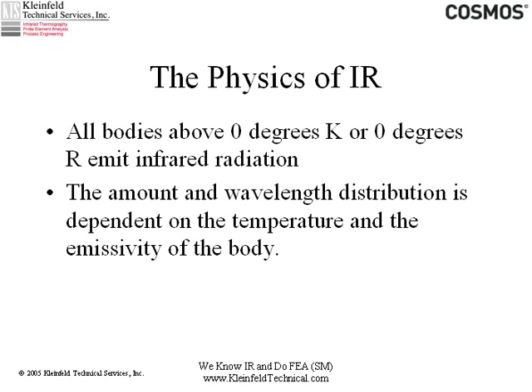The physics involved is that all bodies above absolute zero will emit infrared radiation. The amount of that radiation and the wavelength distribution are dependent on the temperature and the emissivity of the body. Emissivity is essentially a physical characteristic of the surface — things that are reflective have low emissivity, things that are non-reflective have high emissivity, and emissivity ranges from zero to one.